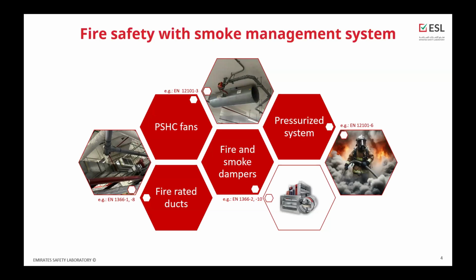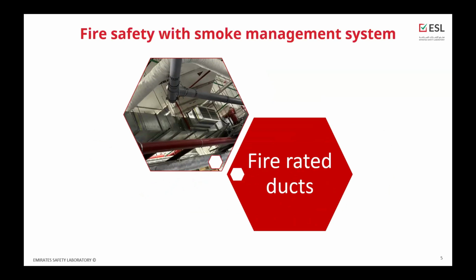So one is, of course, the duct itself, and the second one is the smoke extraction fans, fire and smoke dampers, as well as the pressurized system. Today we will be focusing on the fire-rated ducts only. So in a smoke management system, the fire-rated duct serves several key functions. The first function is containment. They prevent the spread of the fire and smoke between the compartments, which is important in large buildings, for example, high-rise buildings, where the failure of the duct may have fatal consequences.